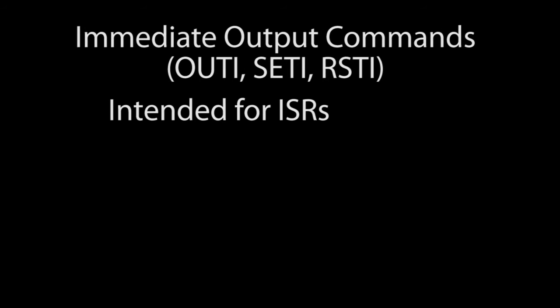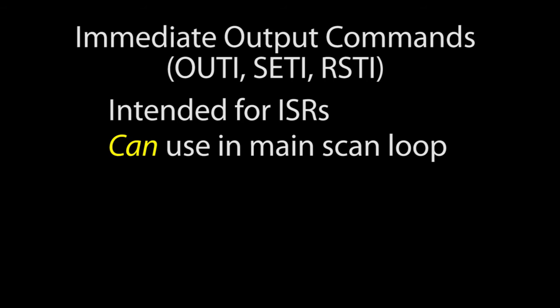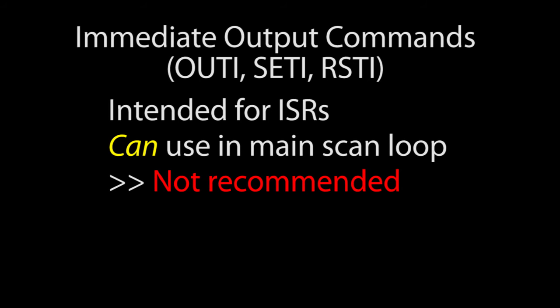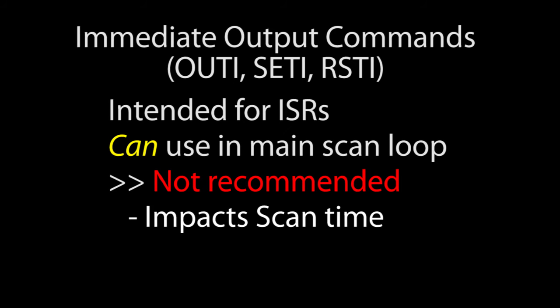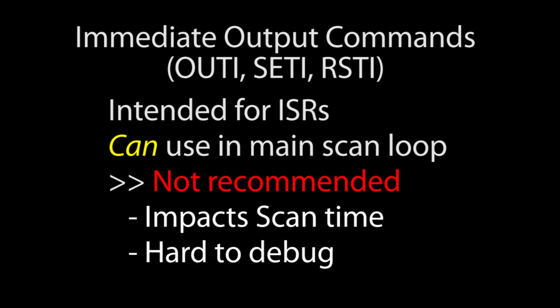One side note, it's tempting to use the immediate instructions everywhere. I mean, why wait for the bottom of the scan for anything, right? Well, you could do that, but it's really not a good idea. PLCs are designed to read the inputs at the start of the scan, do the ladder logic, then update all the outputs at the end of the scan. Using immediate output instructions outside of an interrupt service routine is a good way to get things confused and to make your code really hard to debug. So avoid that temptation.